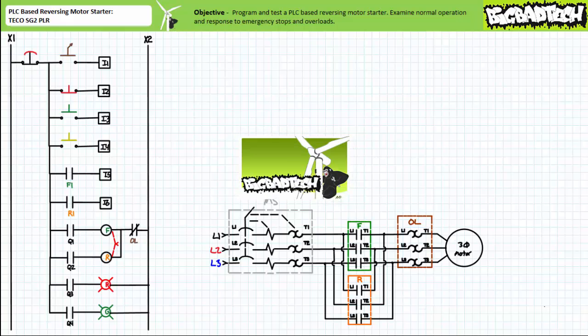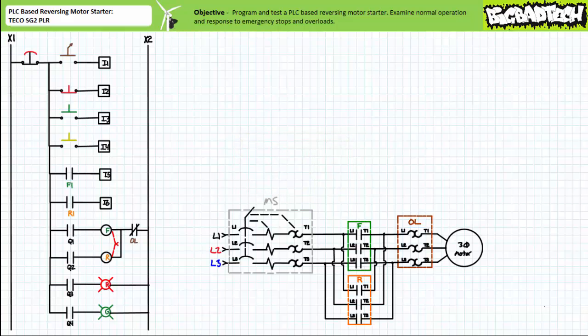We'll examine PLC-based plugging programs in later application exercises. For this exercise, we're using the normally closed momentary contact red push-button on input 2 as our stop button, the normally open momentary contact green push-button on input 3 as our forward button, and the normally open momentary contact yellow push-button on input 4 as our reverse button. The F1 auxiliary contact on input 5 provides feedback about the status of the forward contactor, and the R1 auxiliary contact on input 6 provides feedback about the status of the reversing contactor. This program will not feature plugging, and via electrical interlocking will not allow the opposite state to be asserted if already in a particular operational mode.